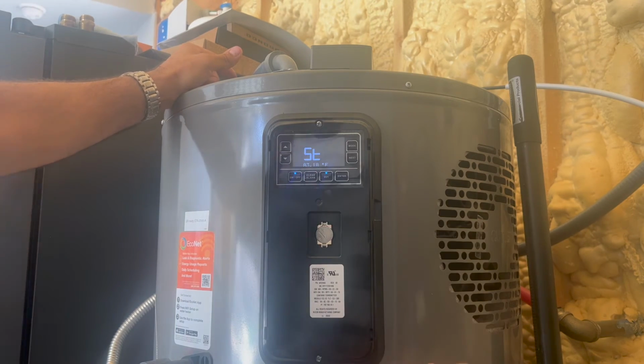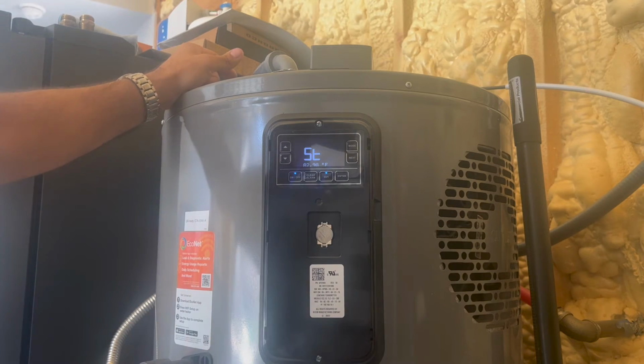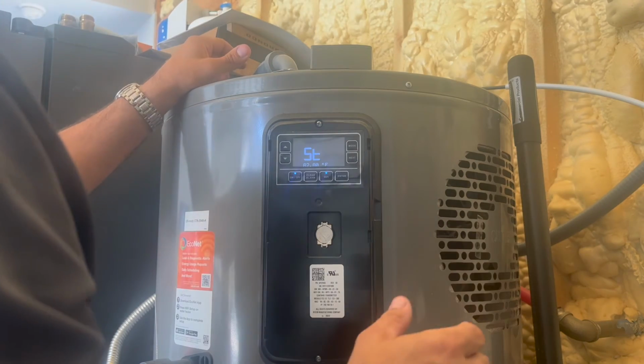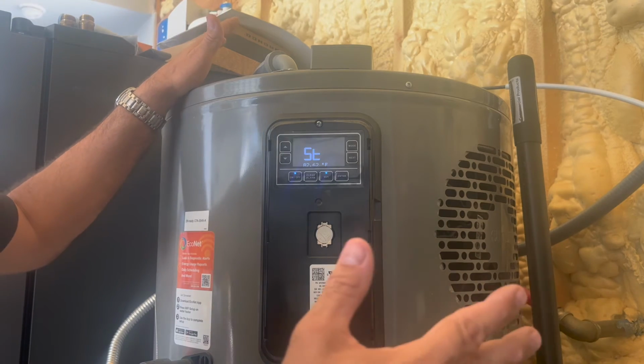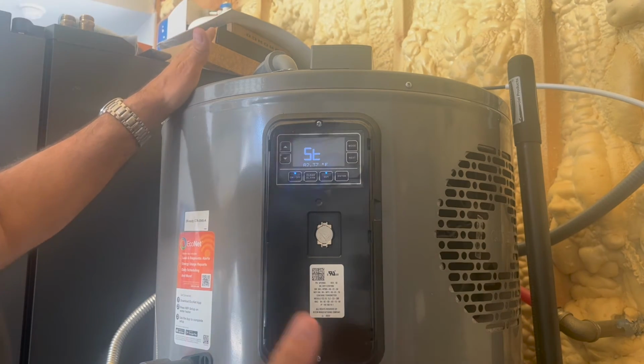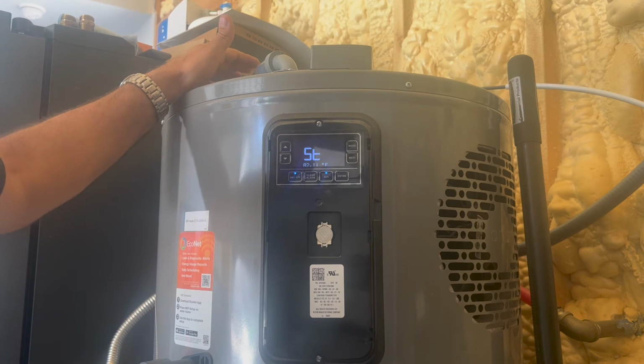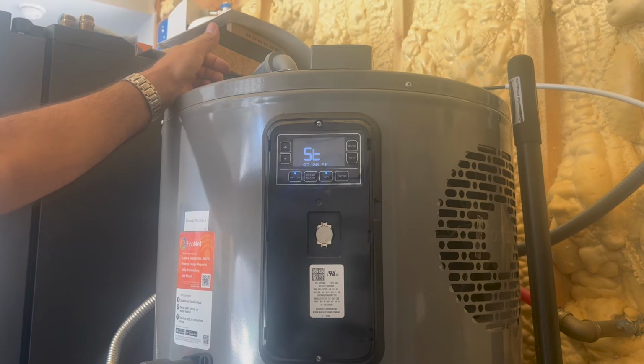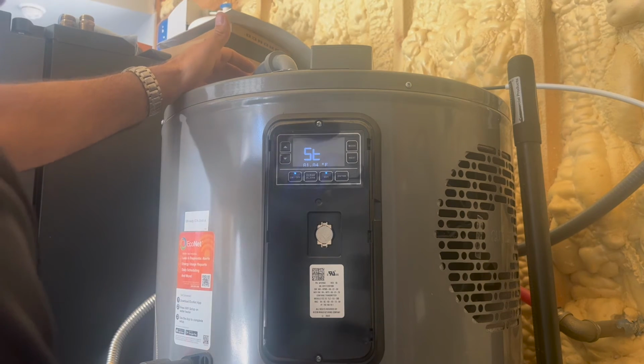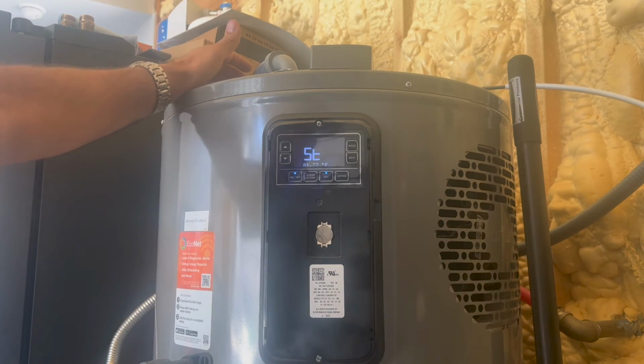If it's running all of the time, there might be a demand issue. It could be an environment issue. We're sitting in 90-degree weather in a garage. This water heater works great out here. Okay, if we're in Seattle in the attic or a basement of a house where it's super cold, it's going to work a little bit harder. It may not even work at all. It may rely heavily on the elements. Let's talk about the elements.